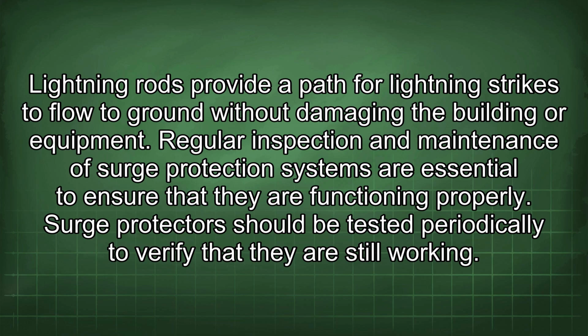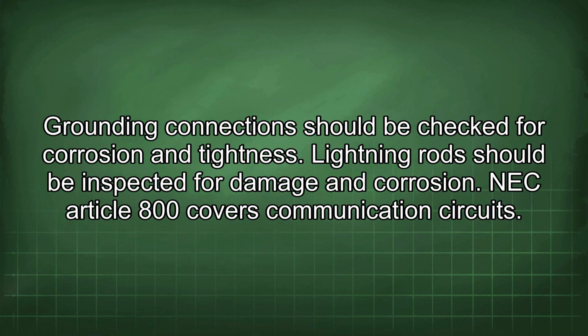Regular inspection and maintenance of surge protection systems are essential to ensure that they are functioning properly. Surge protectors should be tested periodically to verify that they are still working. Grounding connections should be checked for corrosion and tightness. Lightning rods should be inspected for damage and corrosion.